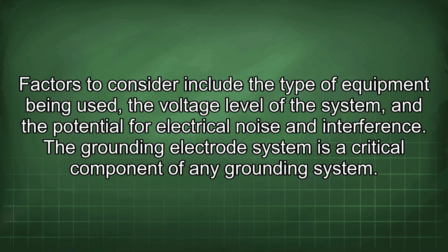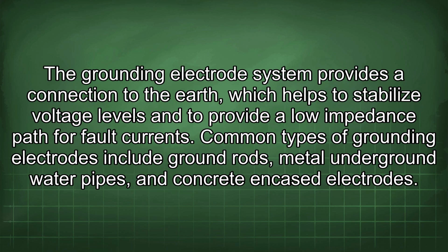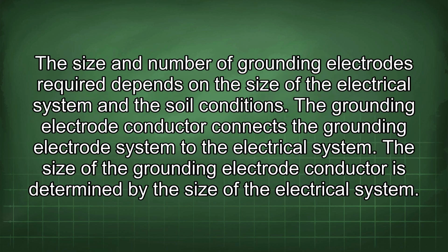The grounding electrode system is a critical component of any grounding system. The grounding electrode system provides a connection to the earth, which helps to stabilize voltage levels and to provide a lower impedance path for fault currents. Common types of grounding electrodes include ground rods, metal underground water pipes, and concrete encased electrodes. The size and number of grounding electrodes required depends on the size of the electrical system and the soil conditions.